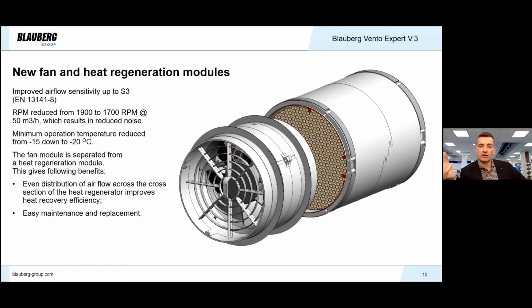Due to the fact that the fan is located at the warm part of the duct, the minimum operation temperature is also reduced from -15 down to -20. So we have widened the diapason of application of the unit, the diapason of operation. The fan module is separated from the heat regeneration module. This gives the following benefits: even distribution of air across the cross-section of the heat regeneration. This improved heat recovery efficiency. And in case of failure, we can replace the fan module only. Previously, we had to replace the whole cartridge together with the regenerator. So now repair will become cheaper and easier, more simple.